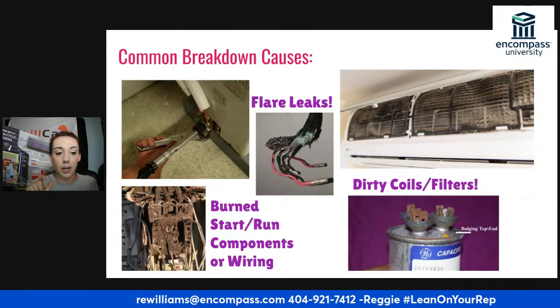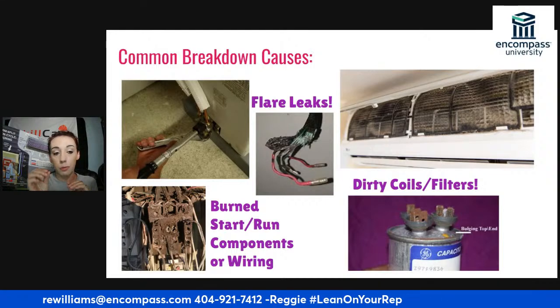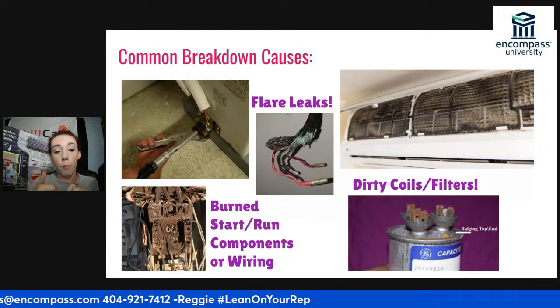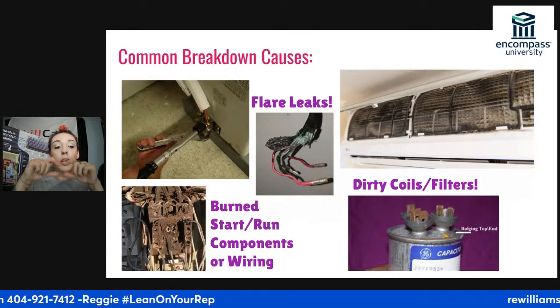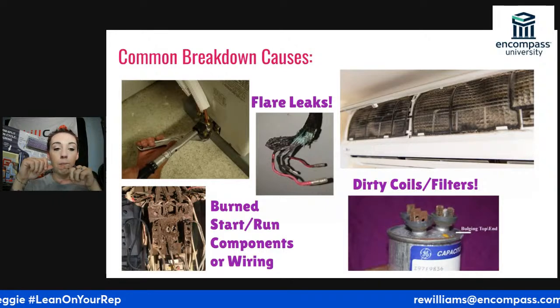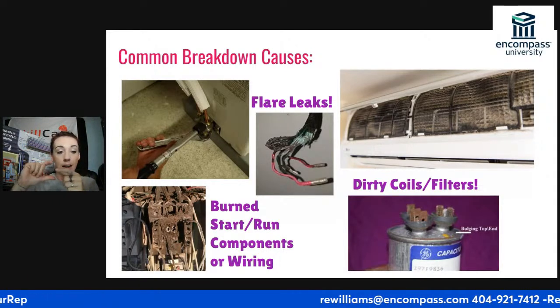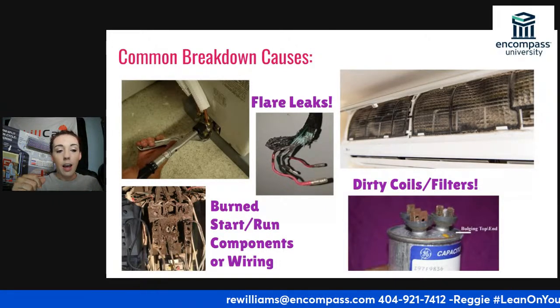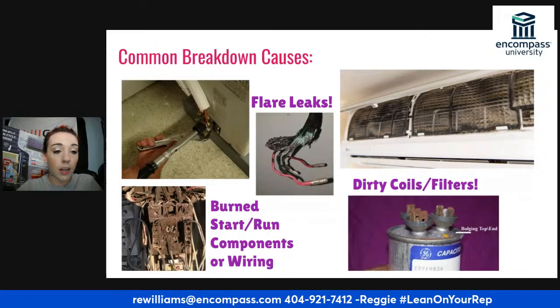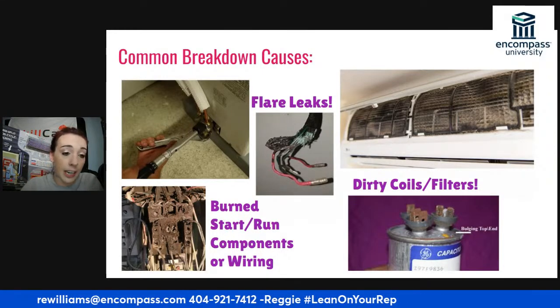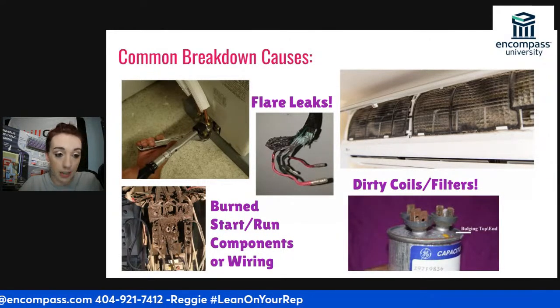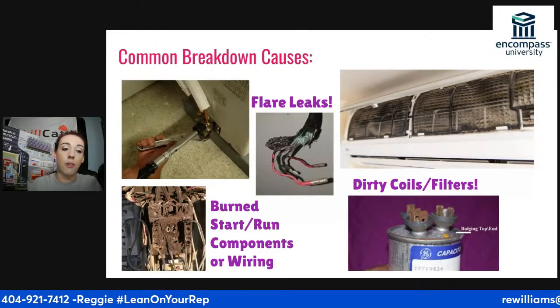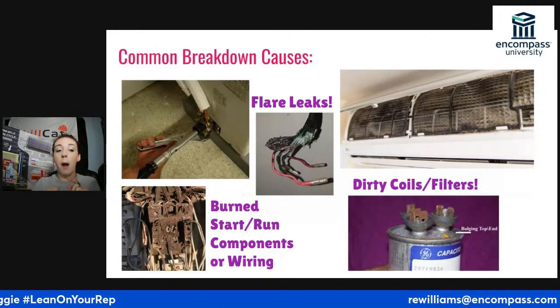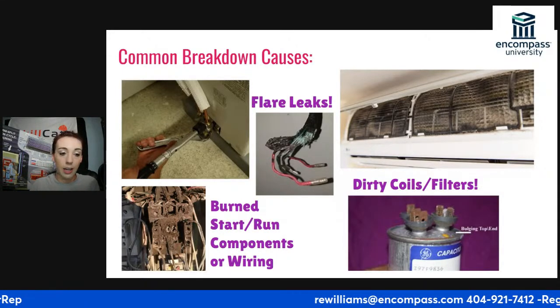If we don't flare it properly, we could have a thinner spot on one side, which will break off once the nut is tightened. We could have a spot where it's too thick, so the nut won't tighten all the way. And we could have issues with torque. We could break off the entire flare connection if the whole connection is too thin. So we need to make sure that we're using a flare tool and using it properly, and knowing what our flare should look like, what it should feel like.